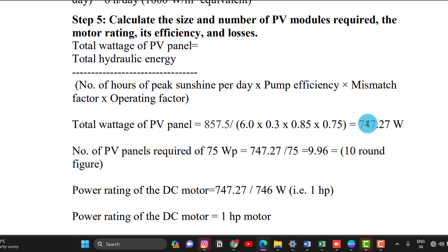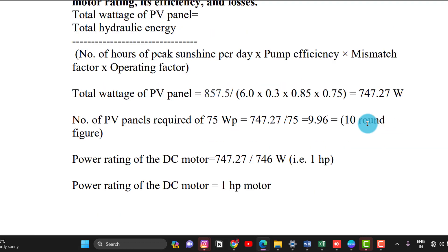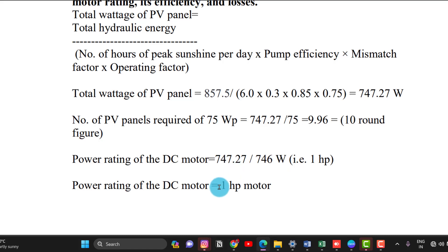With 75 Watt peak panels, 10 panels are required. For the motor: 1 HP requires 746 watts, so a 1 HP motor is sufficient. Summary: 1 HP motor, 10 panels of 75 Watt peak, for pumping 25,000 litres of water per day. Thank you.